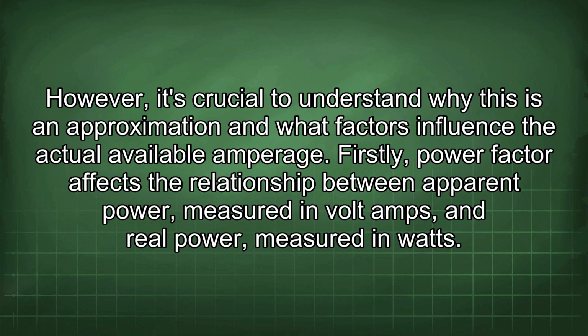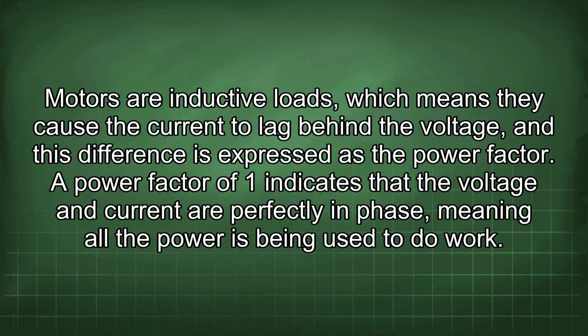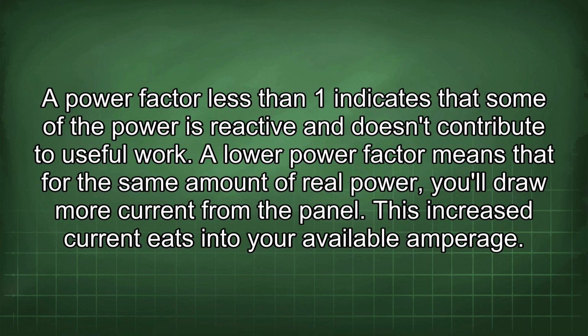Firstly, power factor affects the relationship between apparent power, measured in volt-amps, and real power, measured in watts. Motors are inductive loads, which means they cause the current to lag behind the voltage, and this difference is expressed as the power factor. A power factor of 1 indicates that the voltage and current are perfectly in phase, meaning all the power is being used to do work. A power factor less than 1 indicates that some of the power is reactive and doesn't contribute to useful work. A lower power factor means that for the same amount of real power, you'll draw more current from the panel. This increased current eats into your available amperage.